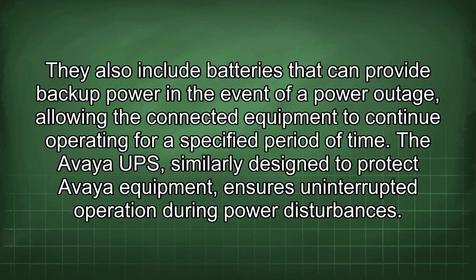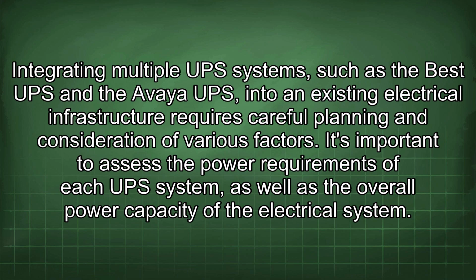They also include batteries that can provide backup power in the event of a power outage, allowing the connected equipment to continue operating for a specified period of time. The Avaya UPS, similarly designed to protect Avaya equipment, ensures uninterrupted operation during power disturbances.